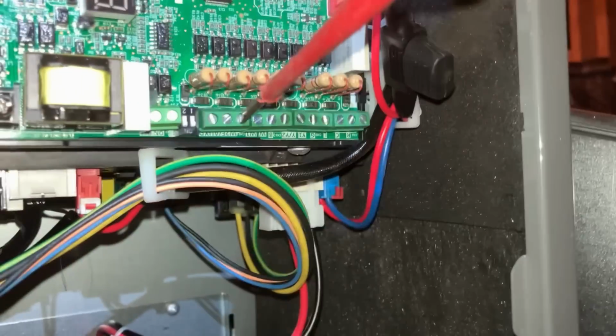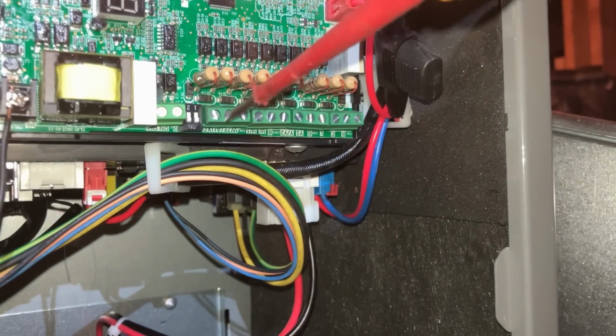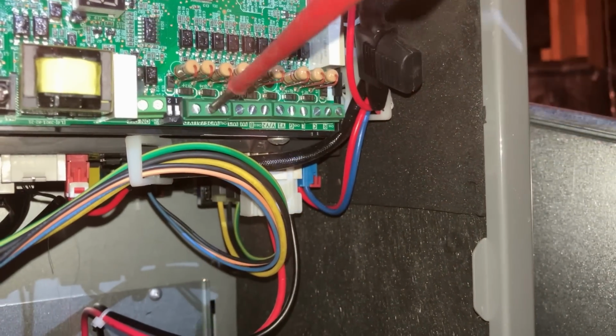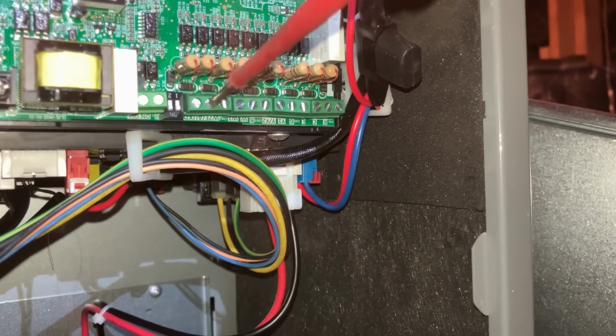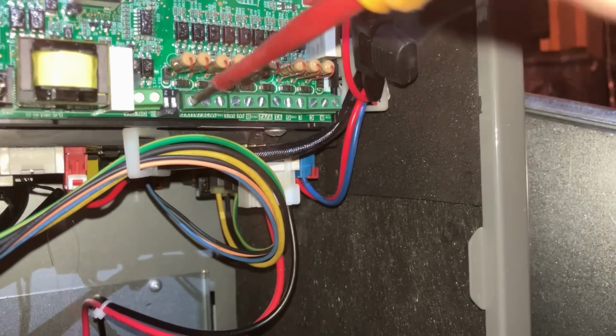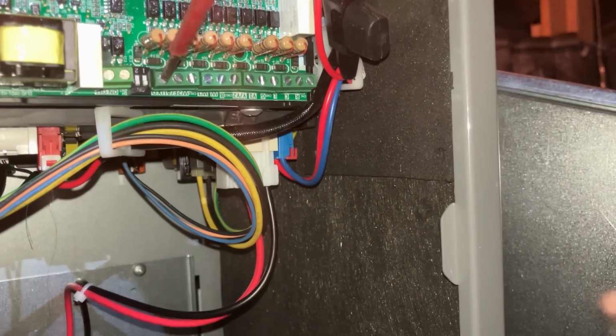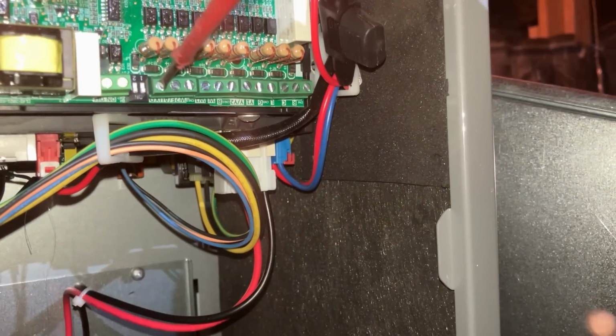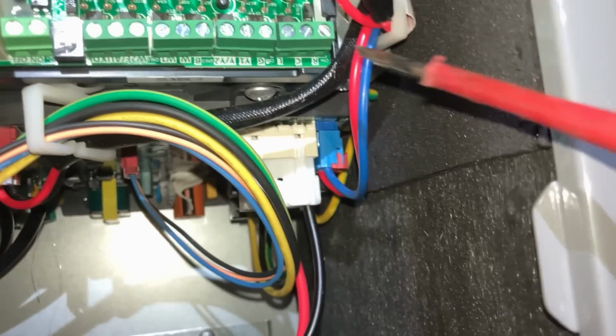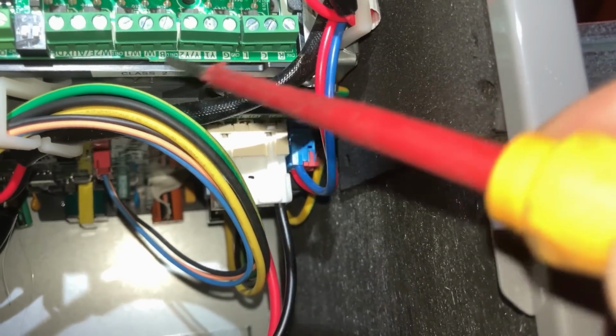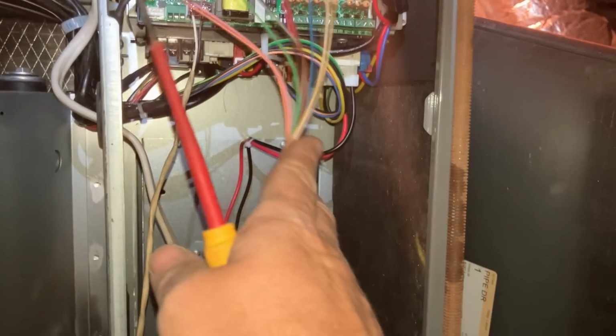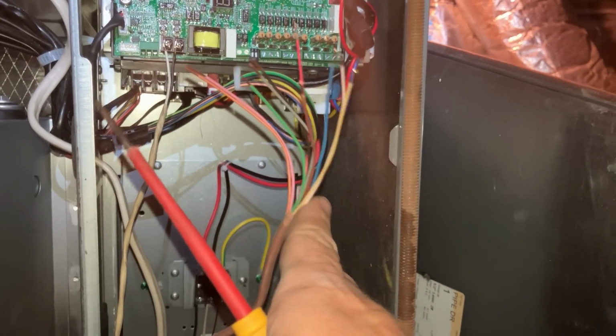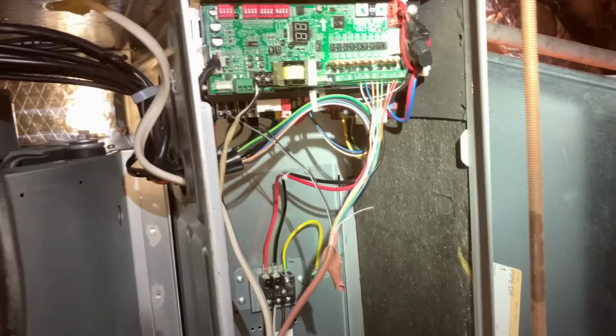And all of these screws on the terminals, well, they're all tight, so you need to loosen them up first, which is annoying because they're always unscrewed and they don't get lost for some reason. So we have R, C, so on and so forth there. There's our conductor wire, 10 conductor wire. We're gonna use 8 of them, and then we'll match this up outside.